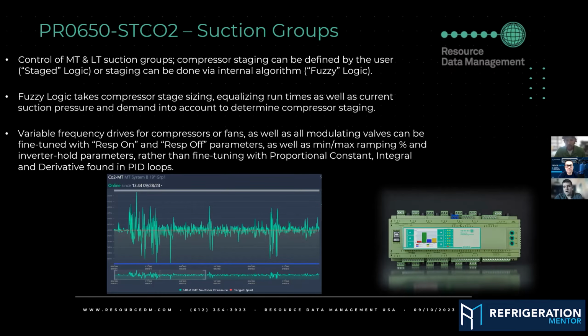Response on and off is a 1 to 60 value. 1 is the slowest, 60 is the fastest. You can start by just setting both response on and off to 30 or 15 or whatever, and that'll probably get you right about where you want to be for control. But if you're seeing spikes that you don't like, you can dial those parameters in to control how it's modulating.